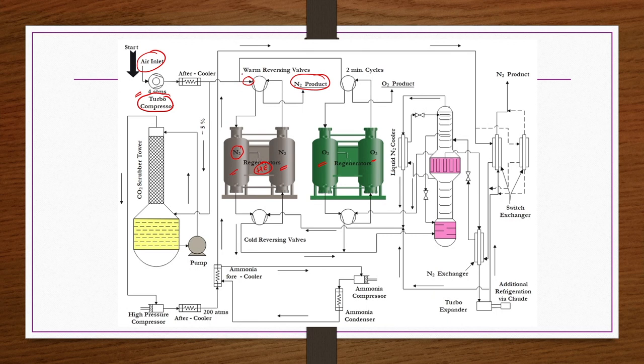Similarly, the cooled air after removing water vapors goes to oxygen regenerative exchangers where the same process takes place — cooling in one exchanger, removing sensible heat from spirals in the other, the cycle continuing. If the outlet has sufficient purity oxygen, it is collected as product; otherwise sent back. Each cycle continues for 2 to 4 minutes, then exchangers interchange their duties. Once sufficiently dry air without impurities is obtained, product O2 and N2 are taken to the fractionation column.